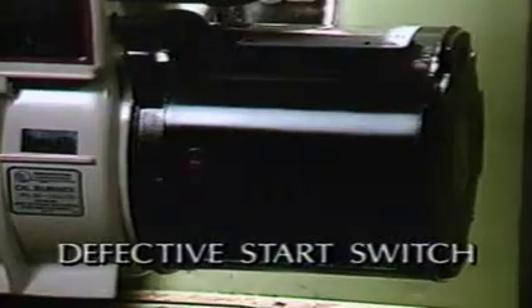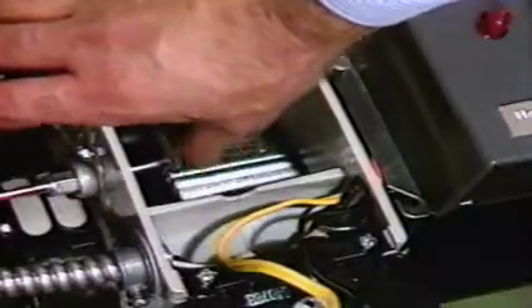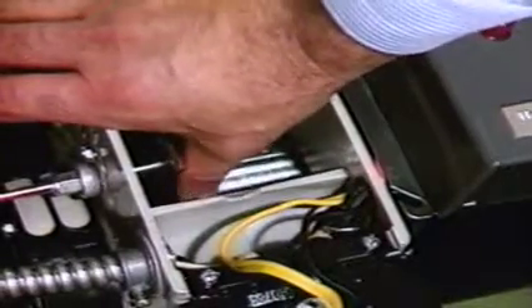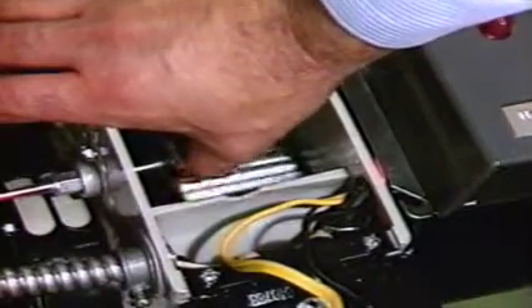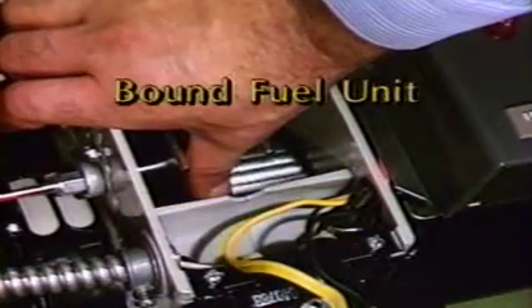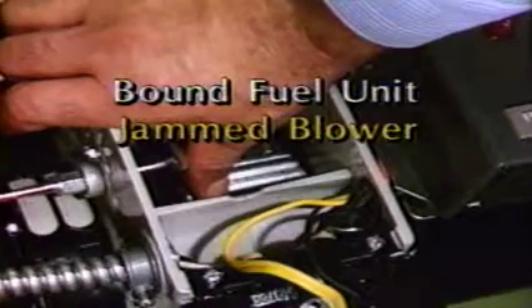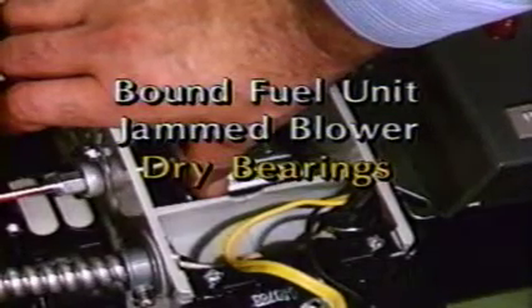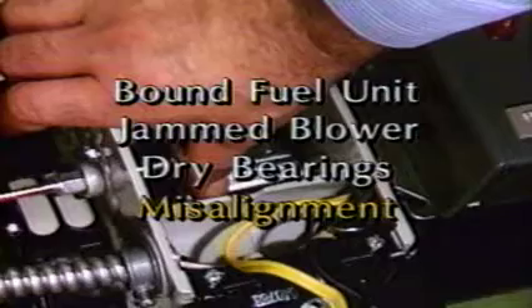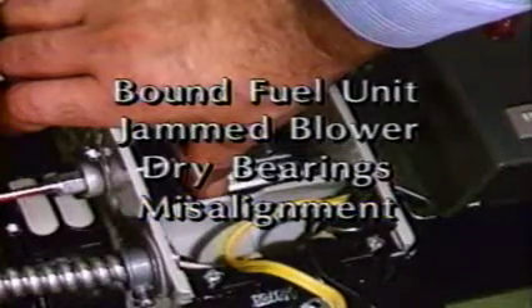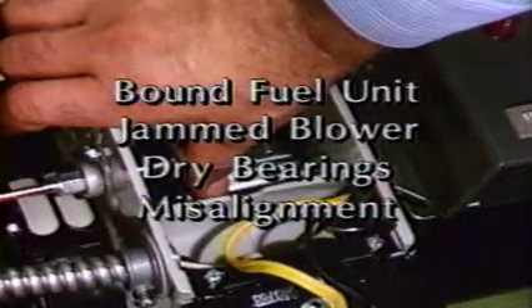But what happens if you hear this? If the motor hums, but the shaft doesn't turn, the start switch may be defective. Turn the power off, then rotate the blower wheel by hand. If it turns freely, replace the motor. But if the blower wheel does not turn freely, you may have a bound fuel unit, a jammed blower, dry bearings, or a gross misalignment of the shaft coupling. Check for these conditions and correct them.